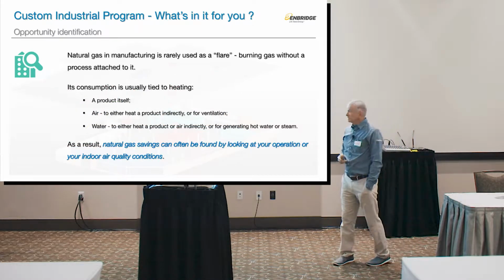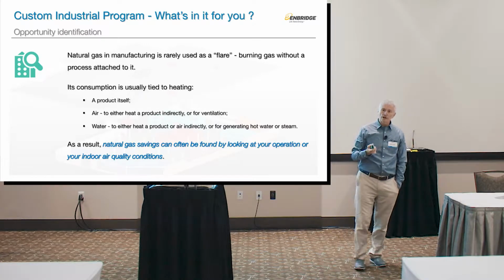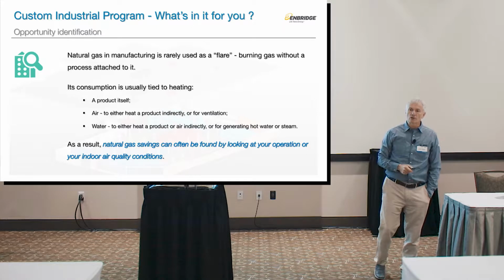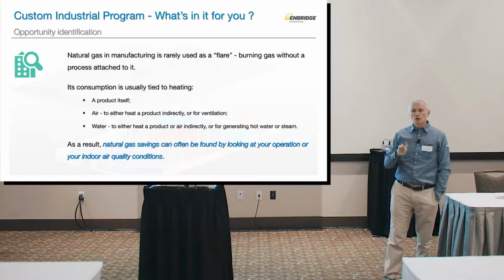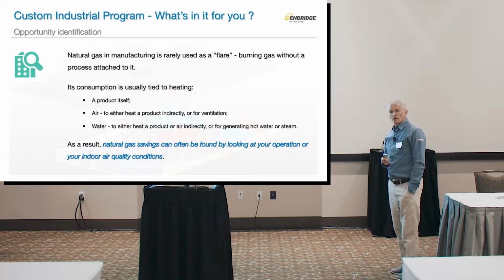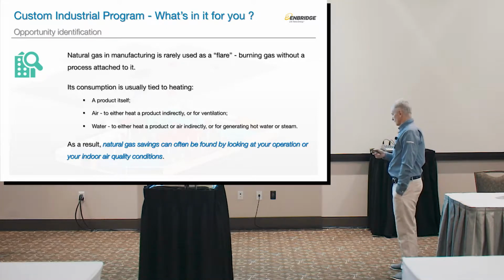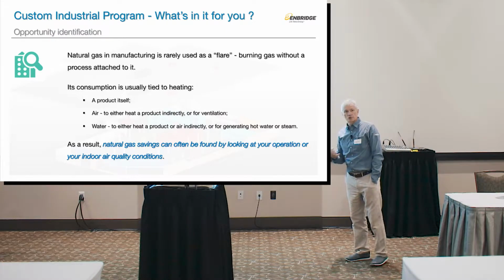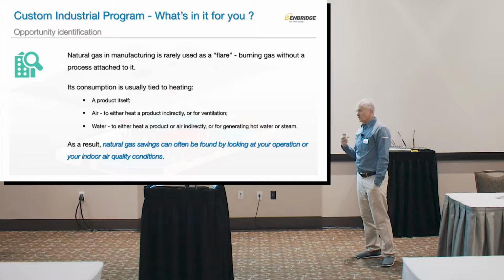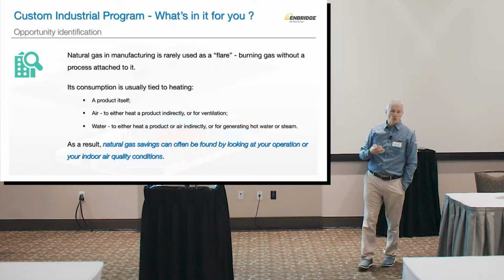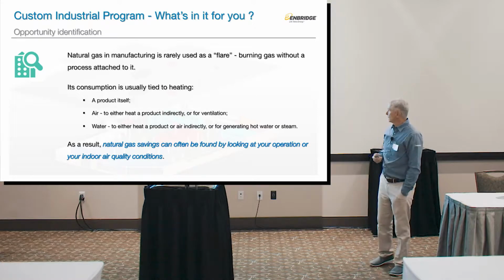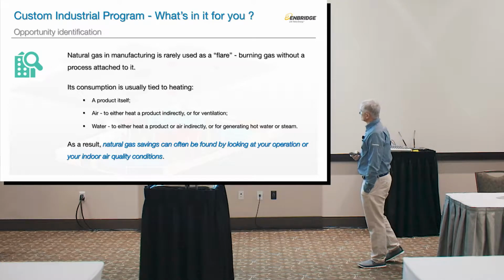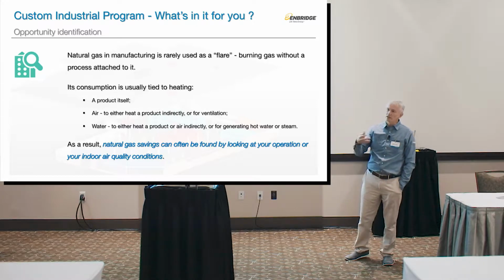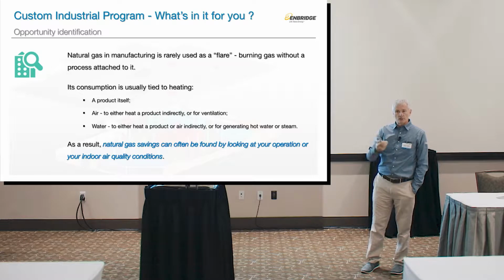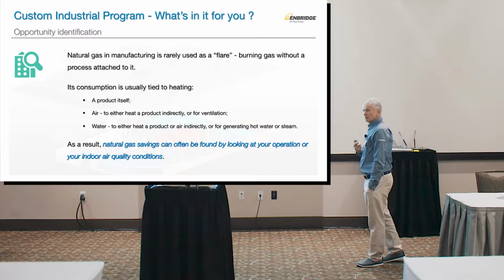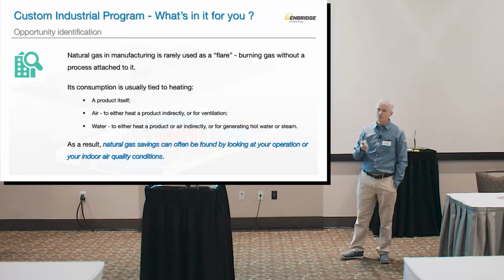The other thing where we look for opportunities: natural gas in manufacturing, you rarely use it as a flare. You don't just fire up the flare and have a nice little barbecue in the backyard. You use it in some sort of a process. And a process for natural gas typically means heating. Whether you heat the product itself in some sort of furnace, and you heat a piece of steel, whether you heat air that then heats the product, or for ventilation or whatever it is that you need air for, or water, heating water. Again, it can be heating the product indirectly. It can heat air indirectly. It can be used as steam. So as a result, natural gas savings are usually found if you look at your processes.